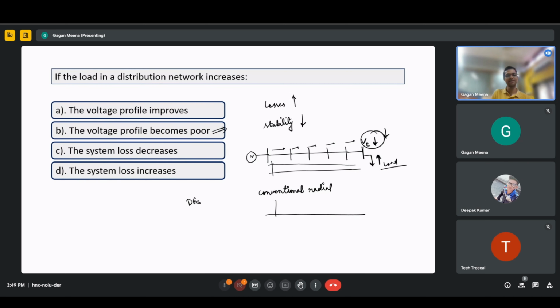Just think what will happen if there is distributed generation or PV, so that at a particular bus there is load plus PV. At a particular time, say daytime, load is very less and PV generation is quite high. Because of high generation, excess generation, voltage at that bus can increase. And it happens, in daytime when solar output is more and the load is less, then at that time voltage can increase at that bus.